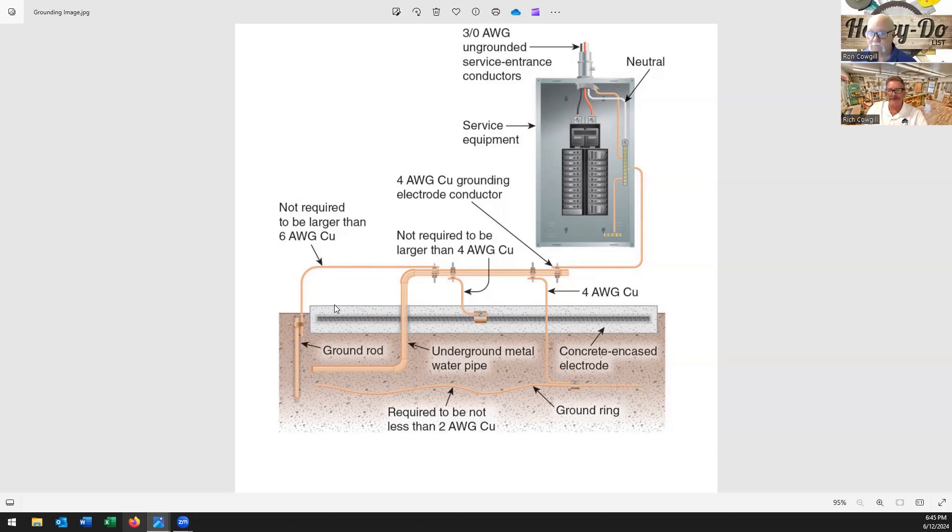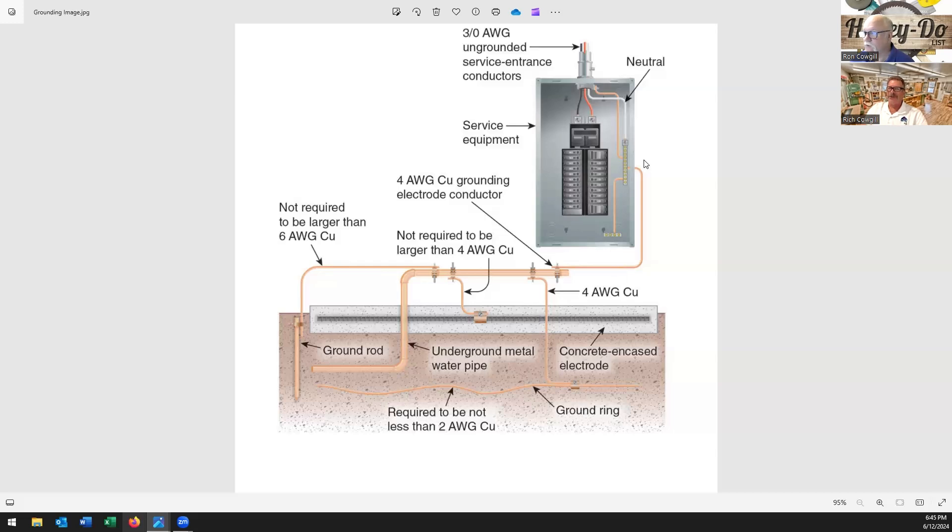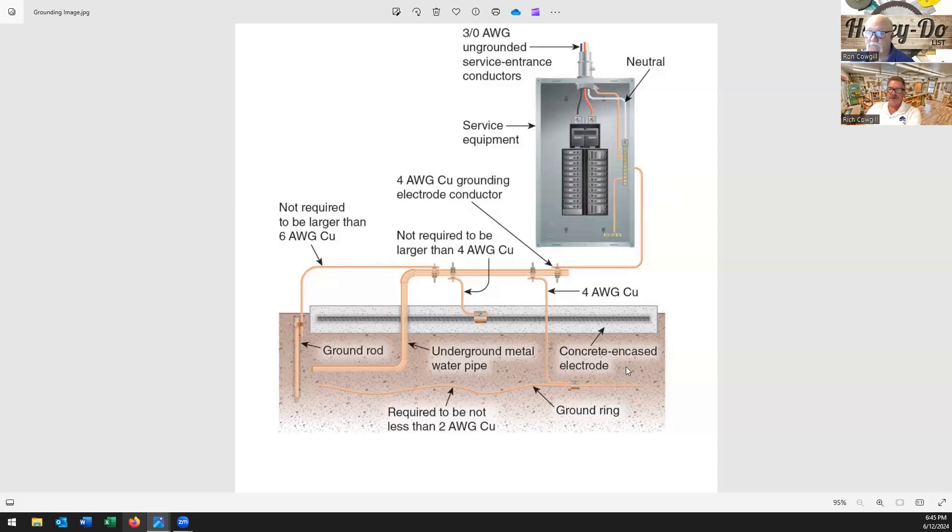So one of the primary purposes of the grounding goes for detection of faults in electrical system and it provides a path for current back from that fault point through the ground to the source's neutral point, which is all that's right here. So when you think about that ground, all that stuff in the ground, it's also going to your neutral bar but it's giving it path to earth or path to ground.